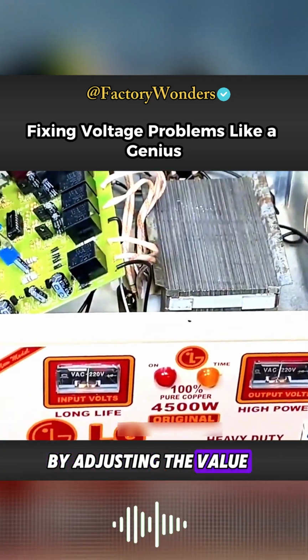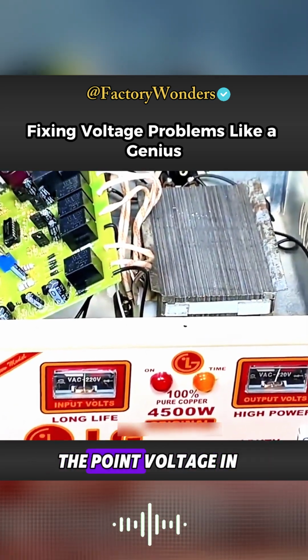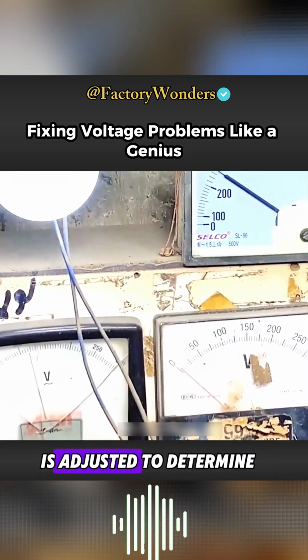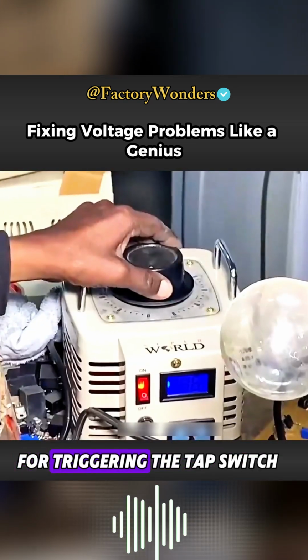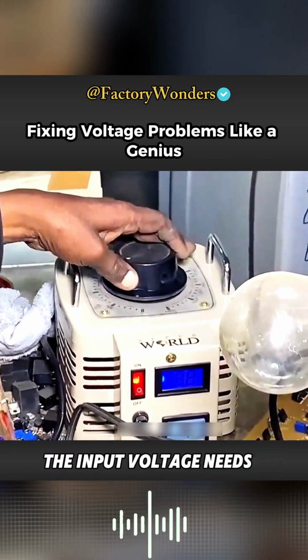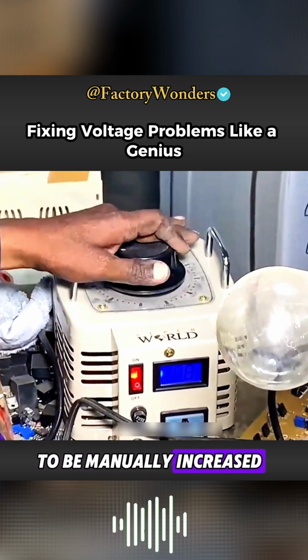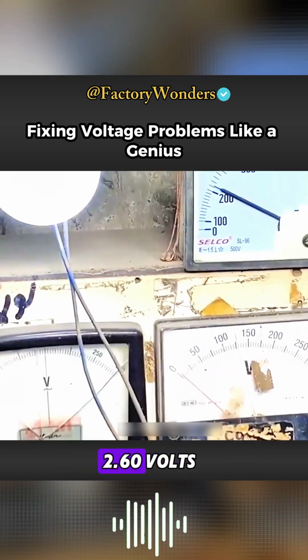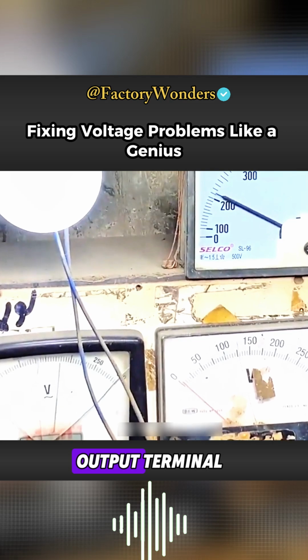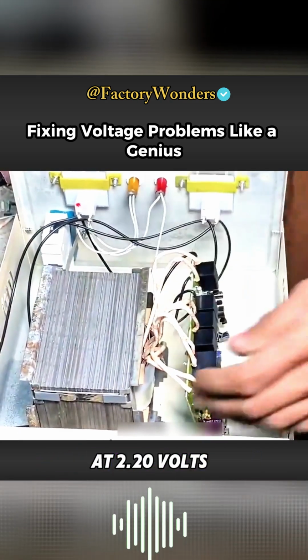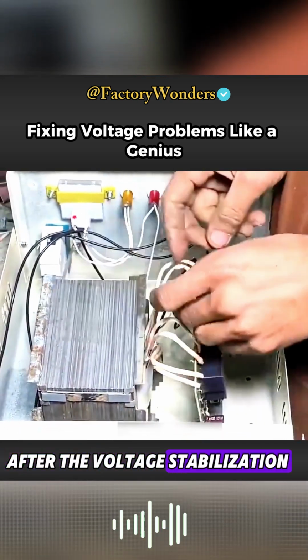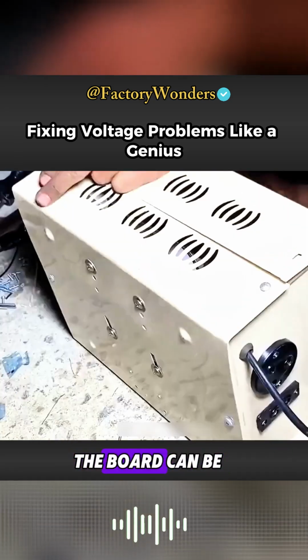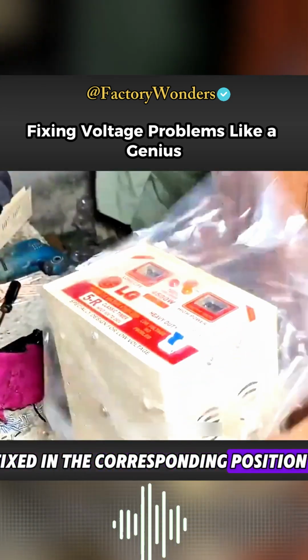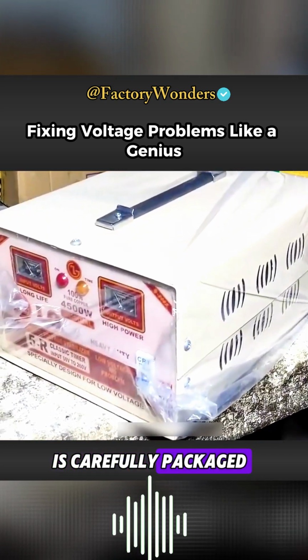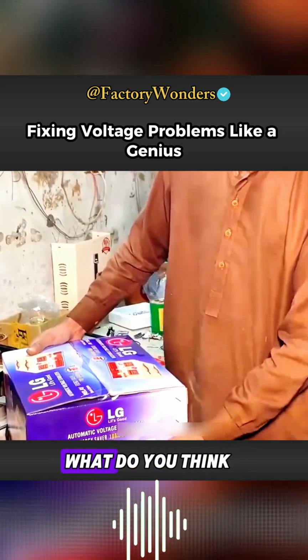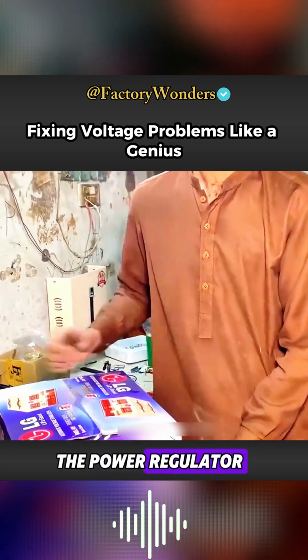By adjusting the value of the adjustable resistor, the voltage in the feedback circuit is adjusted to determine the preset value for triggering the tap switch. In this process, the input voltage needs to be manually increased from 80 volts to 260 volts to test whether the output terminal can always be stabilized at 220 volts. After the voltage stabilization test is successful, the board can be fixed in the corresponding position and then assembled. It is carefully packaged. So after watching the whole process, what do you think of the quality of the power regulator made in this way?